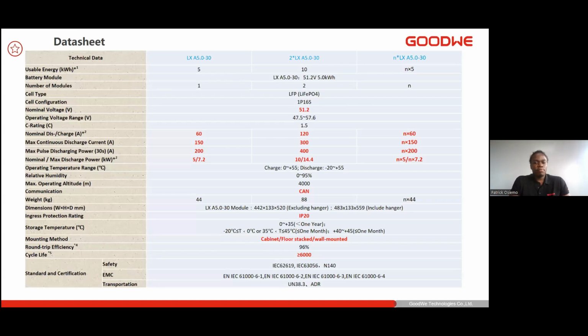Now, we dive into the data sheet, a brief showcasing of it. Notably, I will be brief on this. We have a 1.5C rated battery, low voltage, so 51.2 volts nominal. The battery is powerful. A single battery can do a nominal discharge of 60 amps. But if you want to make use of the C rating, a single battery can output a maximum of 150 amperes continuously. And there's another higher step: the battery can produce 200 amps in impulses of 30-second duration. That's how robust the battery is.